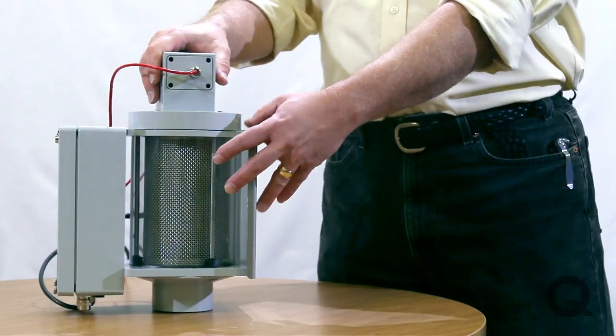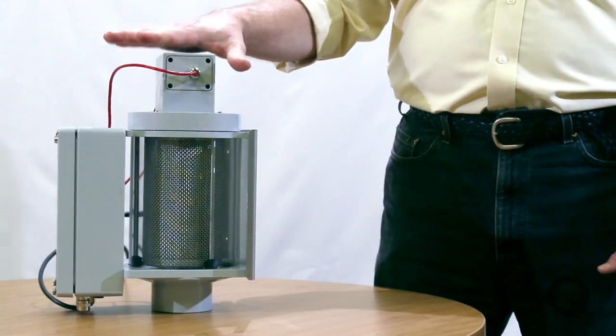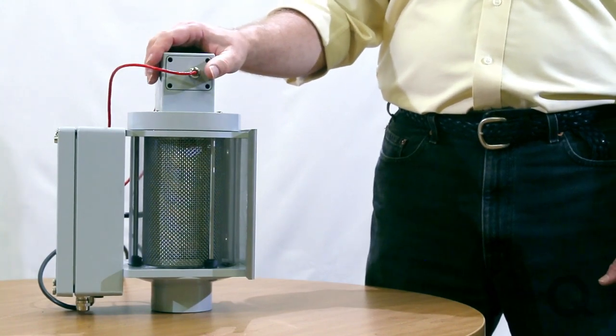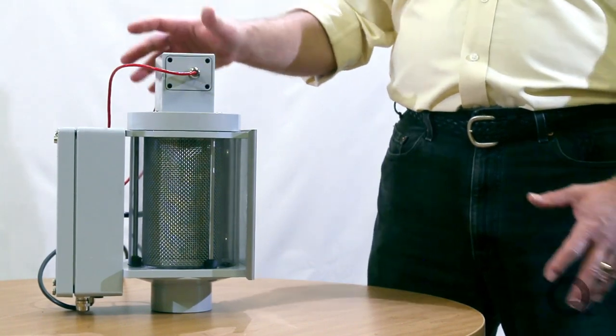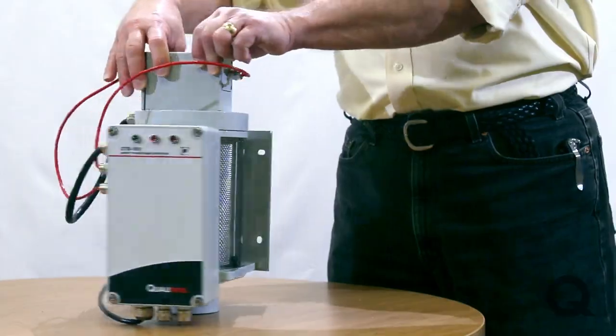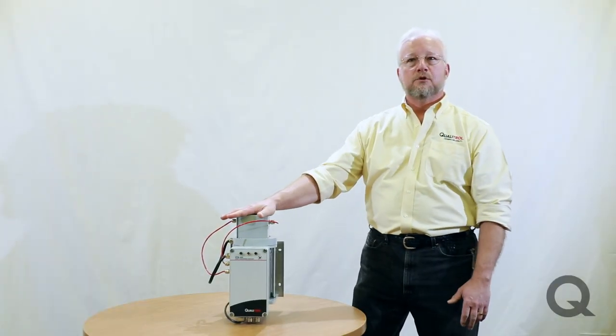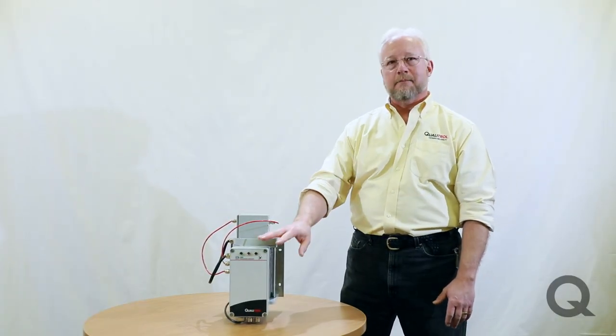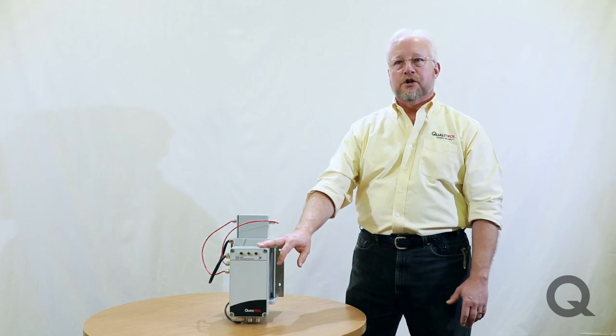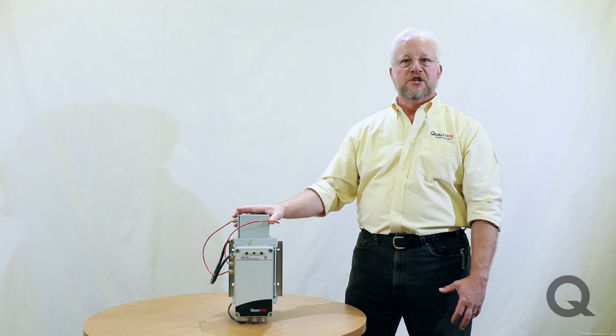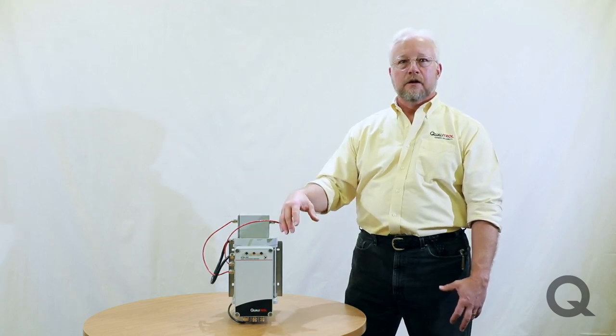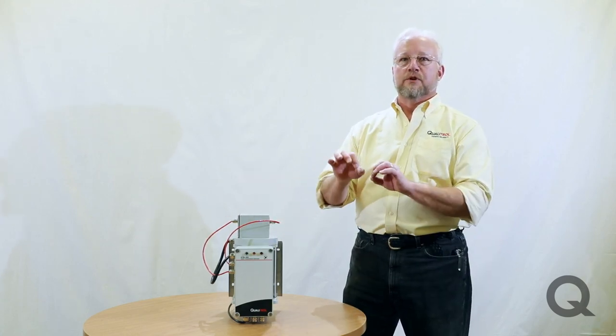What you can't see is that there's a heater that runs through the desiccant. And that is triggered to operate by a relative humidity sensor and timer on the board. So if the relative humidity of the air that is coming out of the conservator tank reaches a certain set point, this will regenerate while the conservator is breathing out.